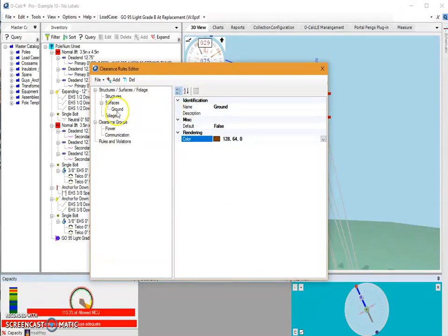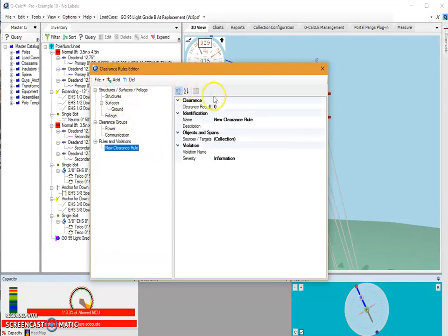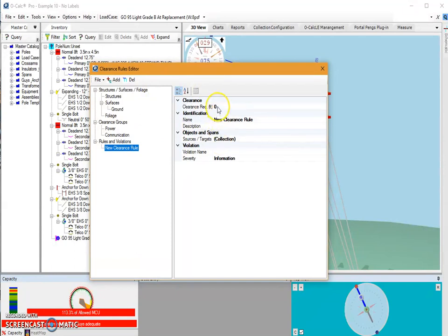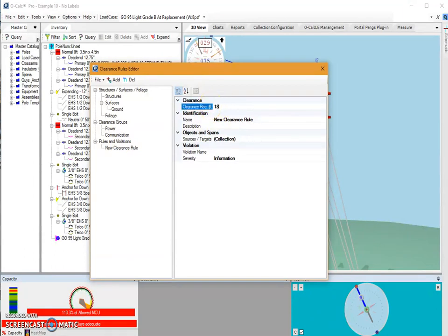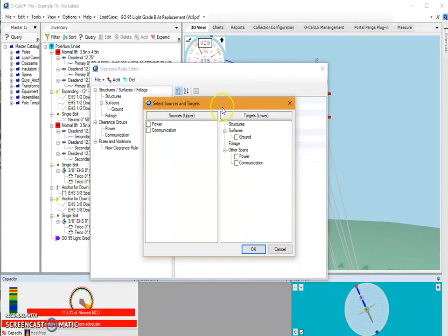So once I've got my ground and two of my groups, I can now create a rule. So once I select rules and violations, I can hit this add button and it will begin generating a rule. Now I'm going to create a ground clearance rule. And I'm going to say that there has to be at least a distance of 18 feet between my targets. My targets I can select by clicking this ellipse button. And I get this window here.